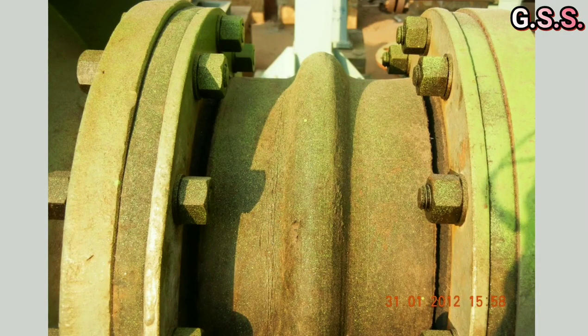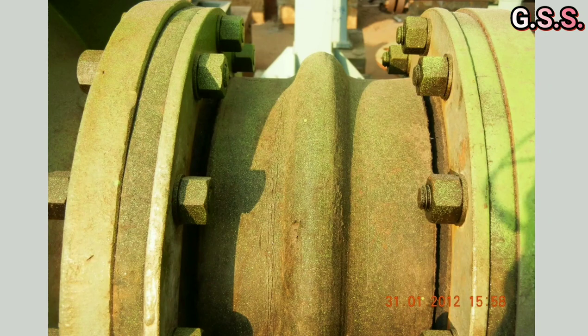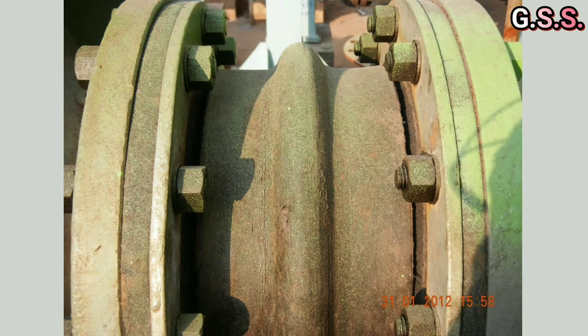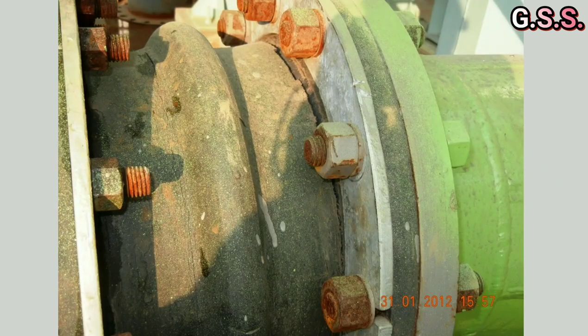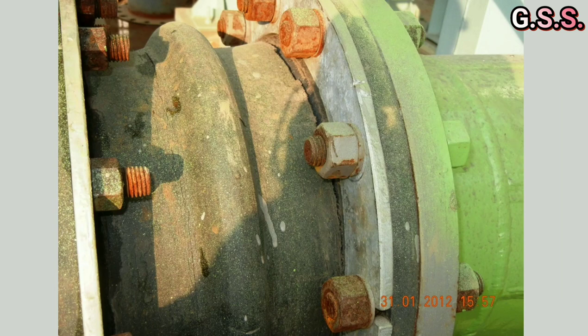Now you can see pictures of few rubber bellows failed due to huge axial expansion due to axial pressure thrust because tie rods were not installed or tie rod nuts were not kept tight.